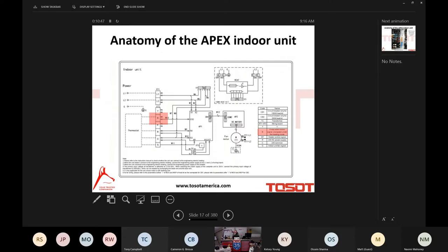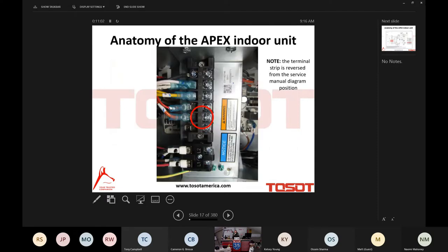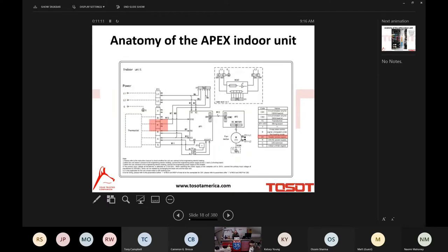Guys, if you're taking notes, let this be the first note of the day. Something different about the Apex indoor unit is that the reversing valve is energized in the heat mode, and that's done through that B terminal that you see here. So first note of the day, reversing valve energized in the heat mode through the B terminal. The W1 terminal is if you utilize the electric heat strip or heater kit, as we call it.